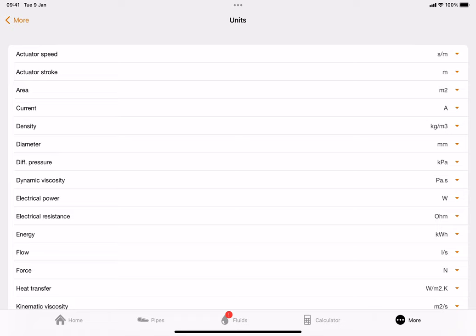You'll see this units page come up. On Android devices you may not have 'actuator speed' and 'actuator stroke' at the top, but the ones you really want to concentrate on to get exactly the same readings as us: the differential pressure must be in KPA. Some people teach in millimeters of head - I teach in KPA because pumps are sized in KPA. So the first one is differential pressure - make sure that is definitely in KPA.